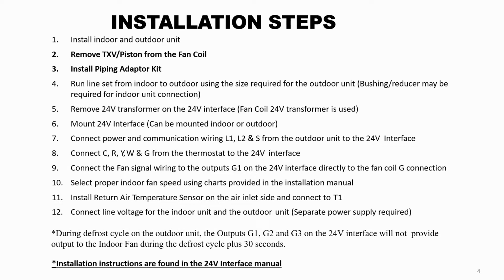The next step, and this is another one that can be done beforehand at your shop or wherever's easiest, is to remove the 24-volt transformer from the 24-volt interface kit, as the combination will use the 24-volt power from the indoor fan coil to power the thermostat and low voltage connections. The next step is to mount the 24-volt interface kit. The interface kit can be mounted indoors or outdoors, and again is going to be dependent on the specific job where it's easiest and most logical to mount it.